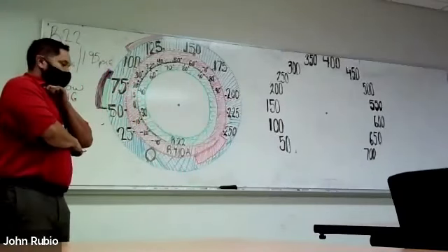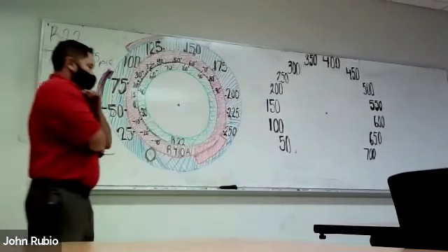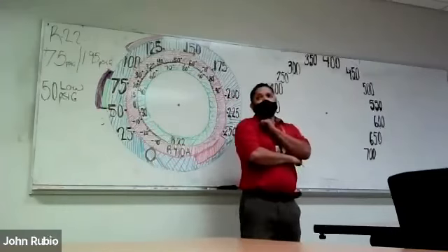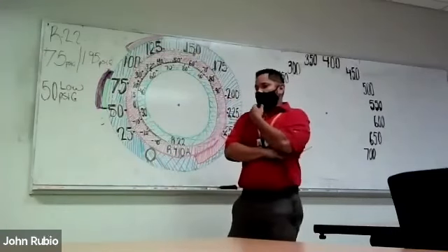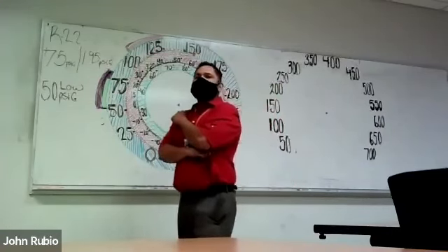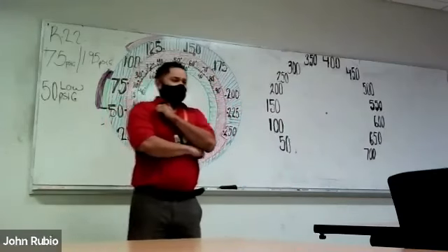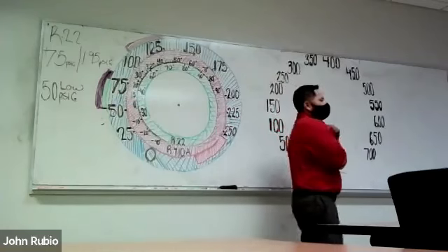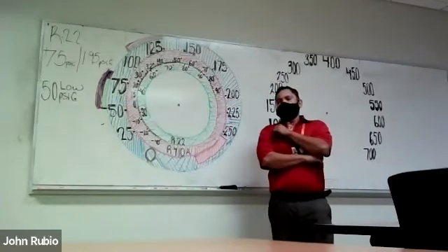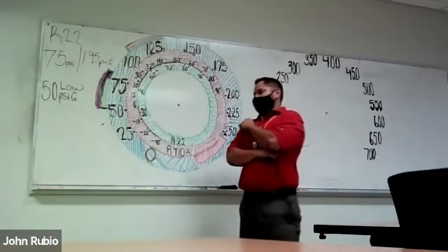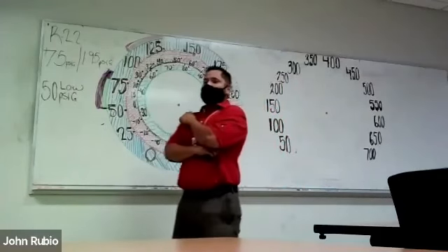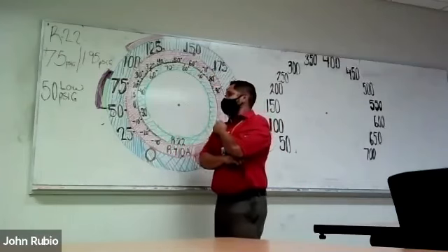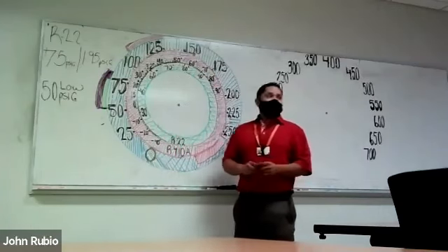Without temperature pressure charts, we can never calculate what our superheat and subcool are. Superheat and subcool is the ultimate in performance. It is the way that we properly put refrigerant into new systems, into systems that carry 410A. To understand this, we have to understand what was different about our predecessor, R22.